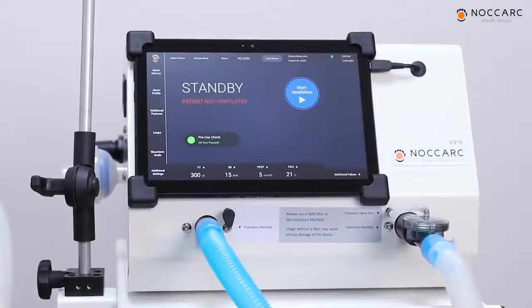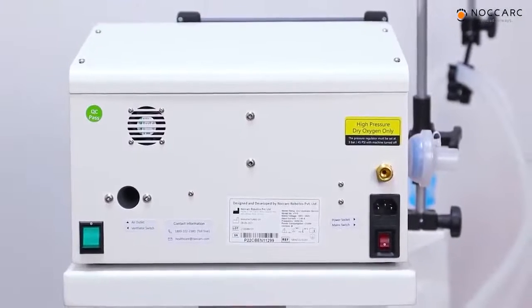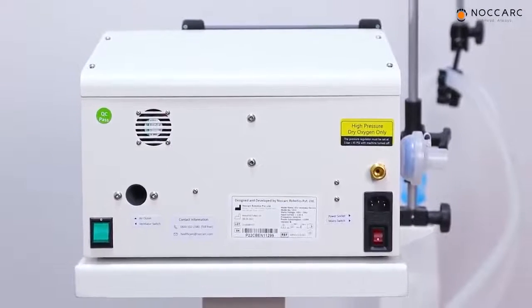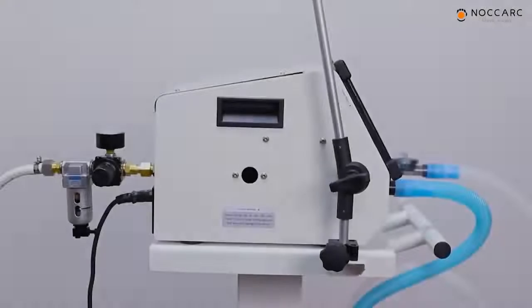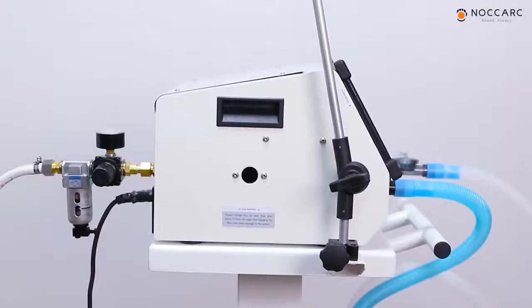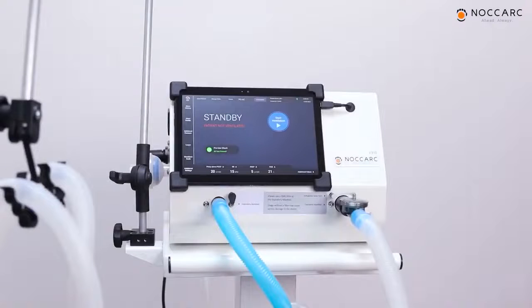The integrated 10-inch touchscreen provides great monitoring and controlling capabilities along with seamless navigation between features through its user-friendly design. On the rear side of the ventilator, red main power switch and green ventilator switch are provided along with the high pressure dry oxygen port on one side and the air outlet port on another side. On the right side, ambient air inlet port is provided from where standard filter can be fitted. On the front side, the 10-inch touchscreen is provided, below which we have the inspiratory and expiratory ports.